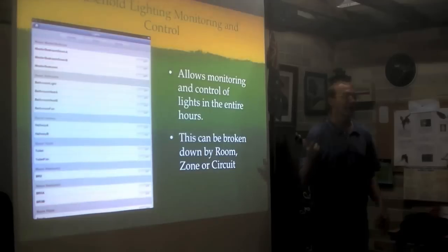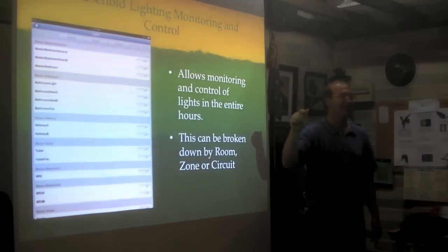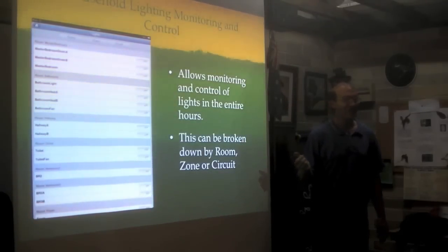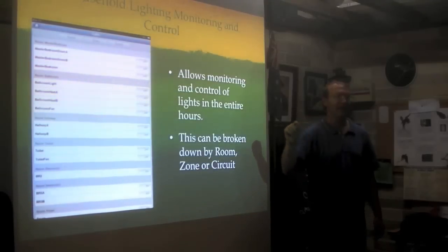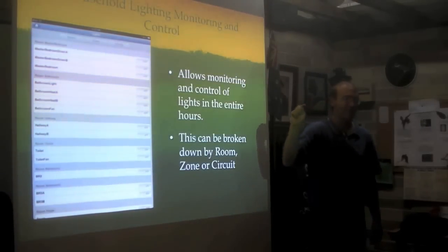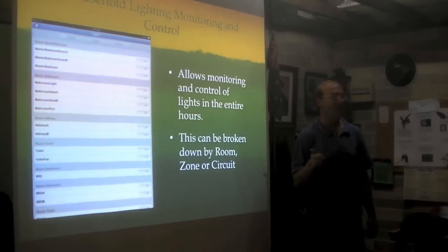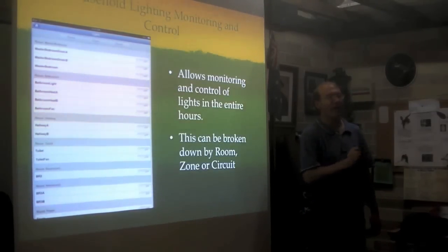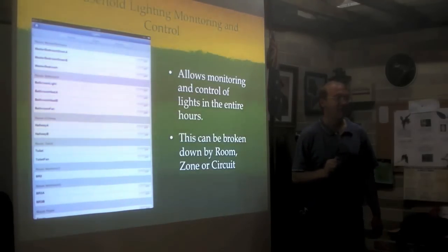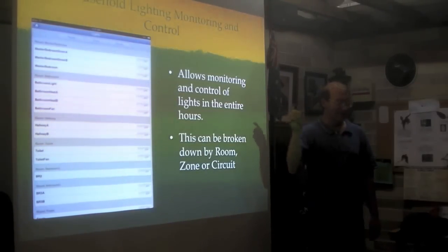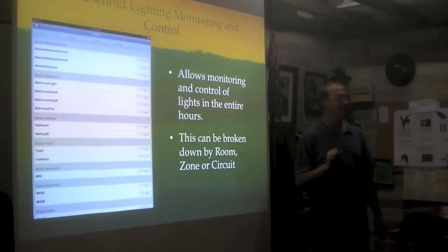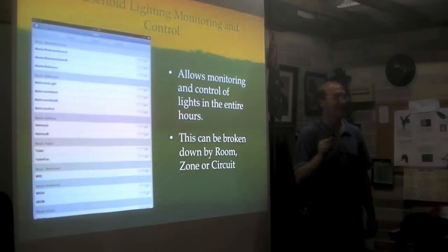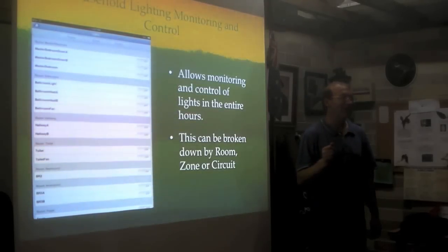In my toilet I've got 2 light switches - one is light only, and the second does light and fan. In the bathroom I've got light and fan, plus 2 heat lamps, 4 heat lamps total. Also in the bathroom, because I cheated and used 1mm wire, I technically can't use it properly - the 1mm on the neutral is a bit small for the heat in the roof, so under regulations I'm not allowed to use all 4 heat lamps if the roof temperature is over 40 degrees, which is over a kilowatt. So, how many people use an IXL Tastic with 4 heat lamps in the middle of summer?